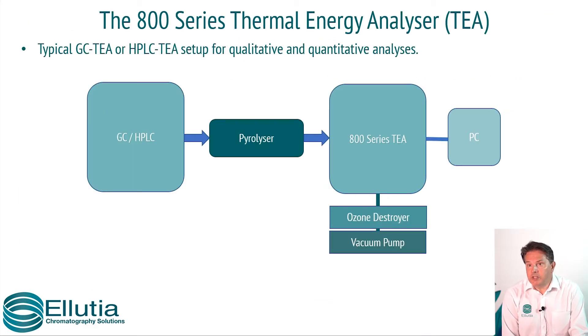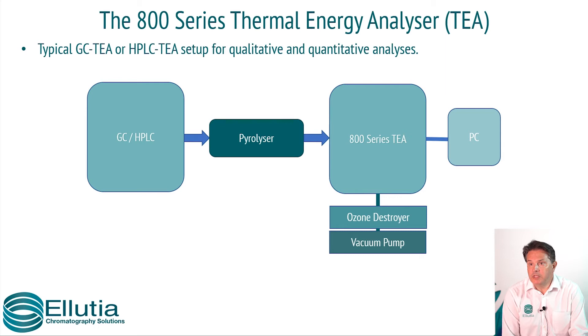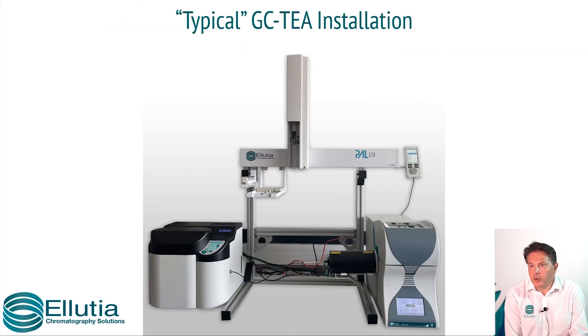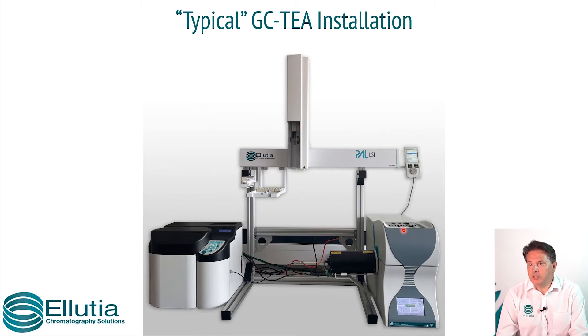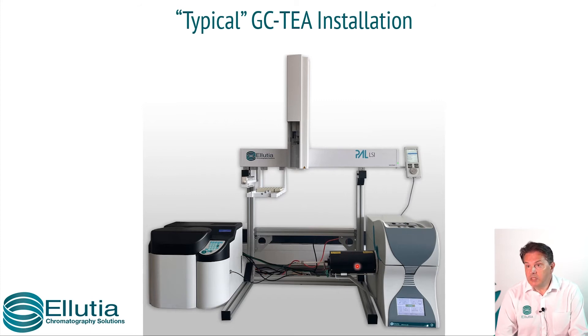This is a generic setup for either a GC or HPLC system. The column effluent enters a pyrolyser where it is heated at temperatures in excess of 500°C. This will break off the nitrosyl group, which is then detected within the TEA. This is a photograph of a typical GC-TEA system. We have the Ellutia PAL, which performs the injection into any GC. The pyrolyser interfaces into a GC through the transfer line port, so this can be interfaced on almost any commercially available GC. Within here it is heated, and then the nitrosyl group enters the TEA.